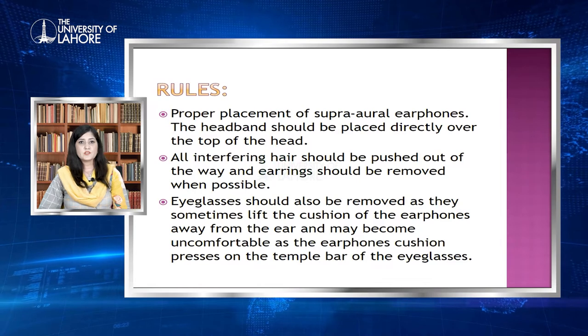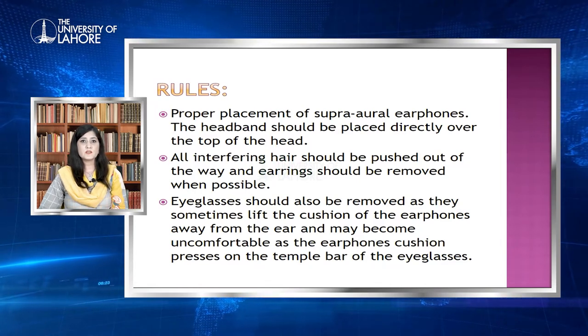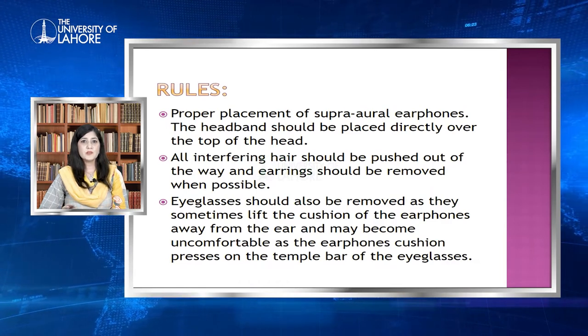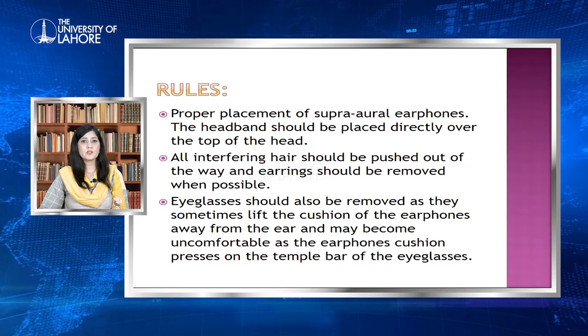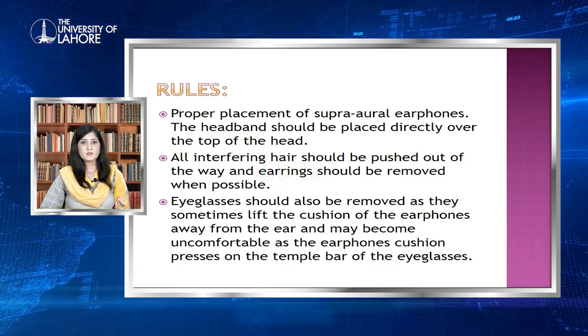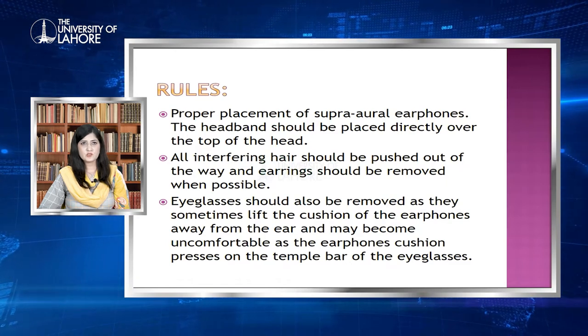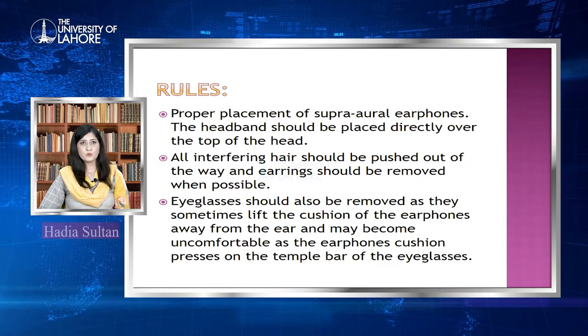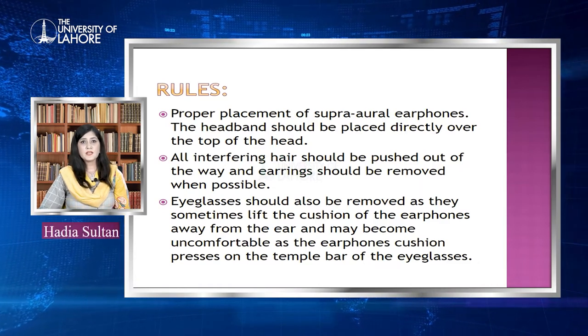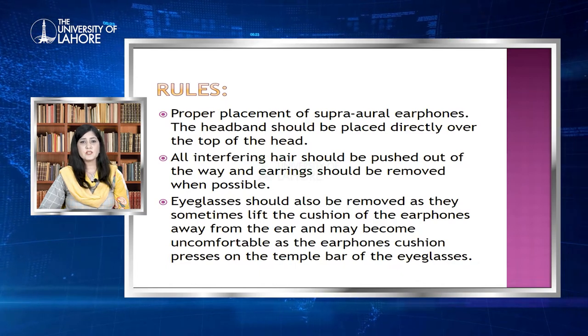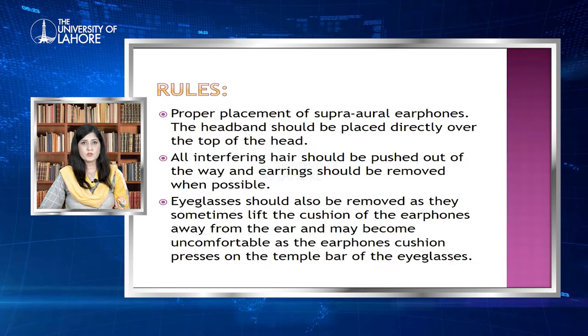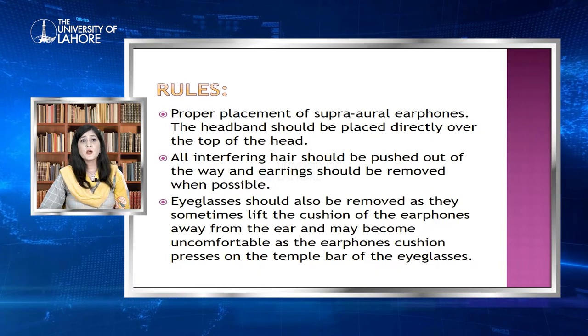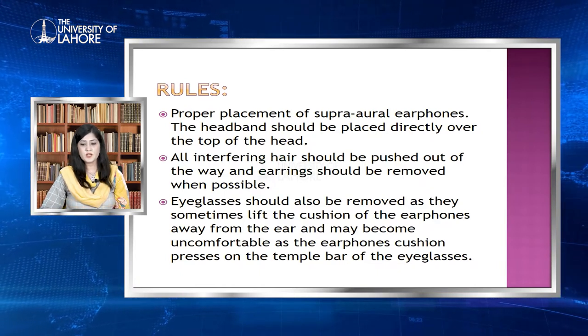Regarding the rules of air conduction audiometry: the placement of headphones should be carefully done by the clinician or audiologist performing the pure tone audiometry procedure. All interfering hairs should be pushed out and earrings should be removed when possible. Eyeglasses should be removed from the patient, though if they are comfortable with their eyeglasses, you should not remove them. Sometimes the earphone presses on the temple bar of the eyeglass, causing discomfort.